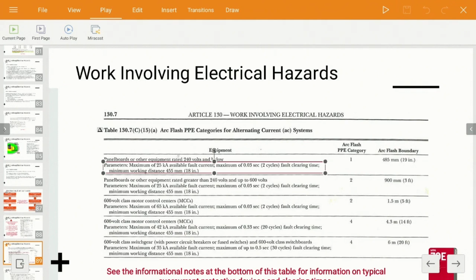So my question to you is, you go to get a 240 volt panel, are you going to know what these parameters are? No, you're not. You're just not going to know. And remember, this does not cover arc in a box type things like panels. Does that make sense? So don't use this gear unless you have to know for a fact what those parameters are in the gear in real life. So instead, what we're going to want to use is the analysis method. Now, some instructors will say for molded case circuit breakers, they typically will follow those parameters.